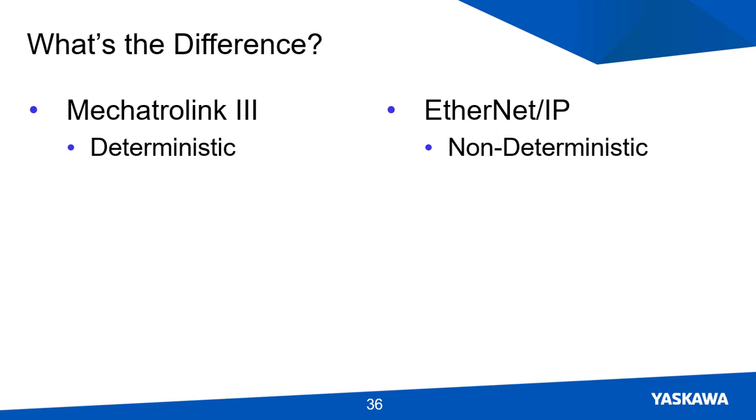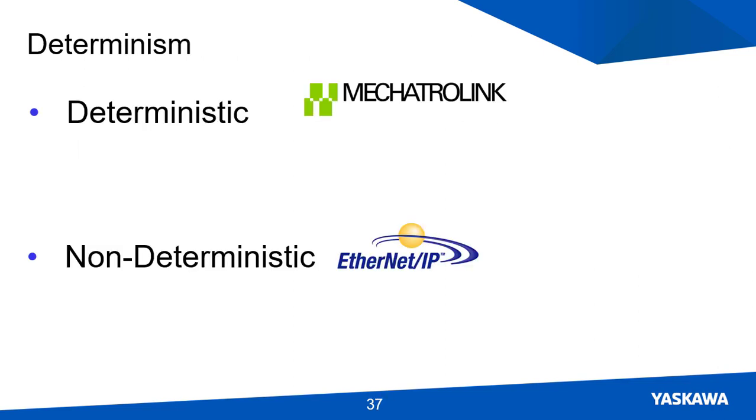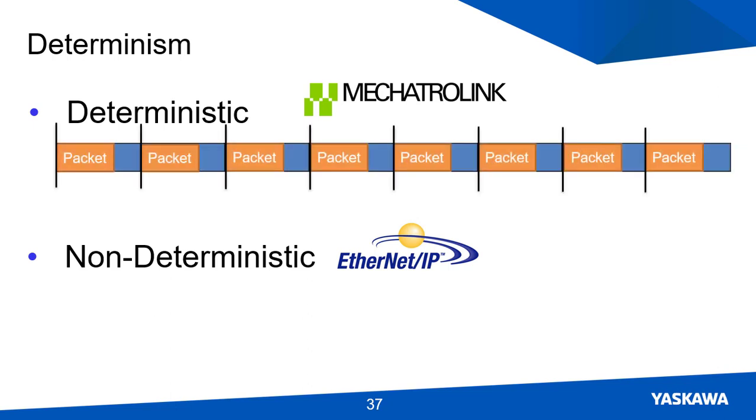So what's the difference between Mechatrolink 3 and Ethernet IP interface modules? I have made mention of both of them up to this point, but which one should be used in which scenario? To start off, Mechatrolink 3 is deterministic, compared to Ethernet IP, which is non-deterministic. Deterministic networks provide better communication for motion networks because the transmitted data being sent is scheduled and received at a low latency rate.